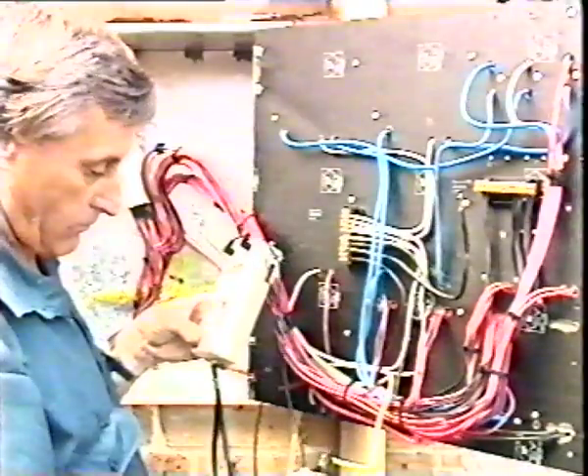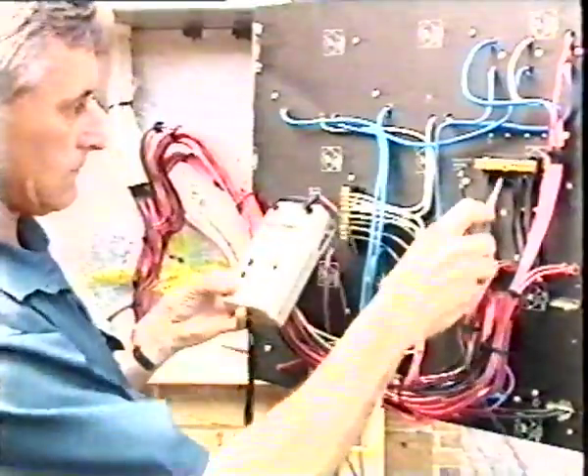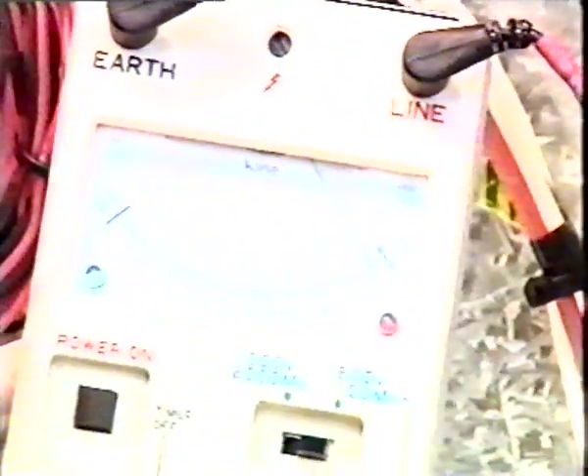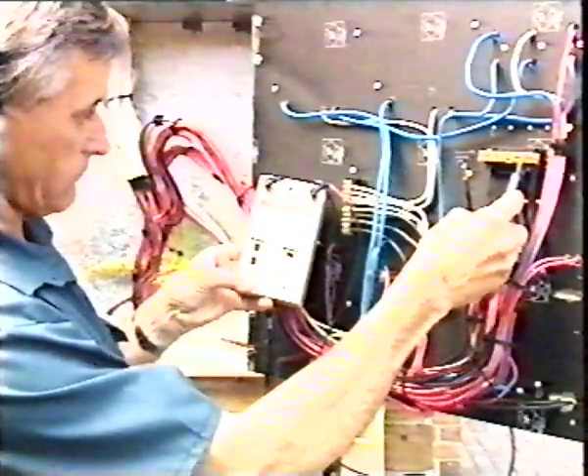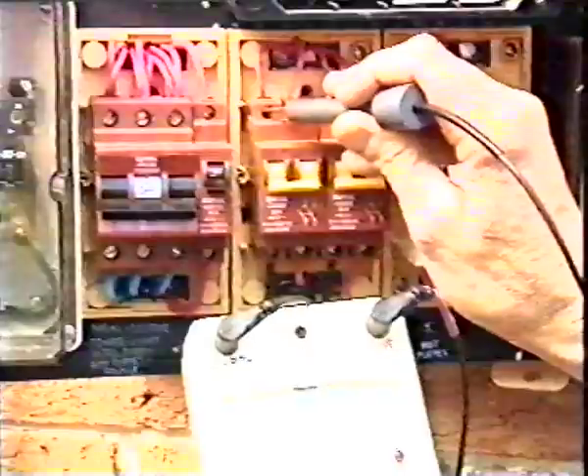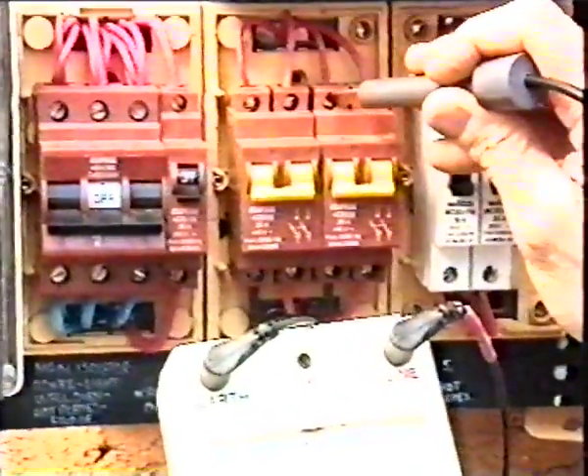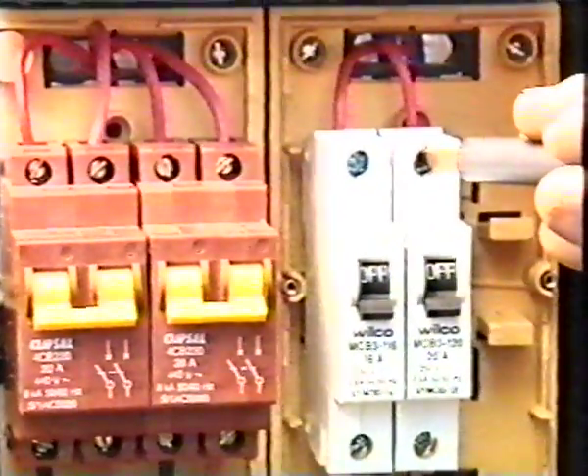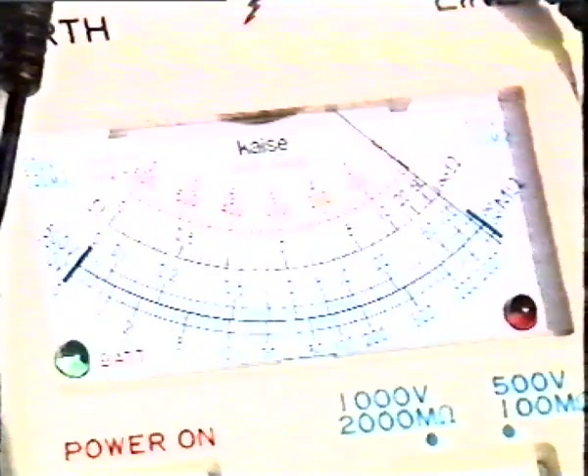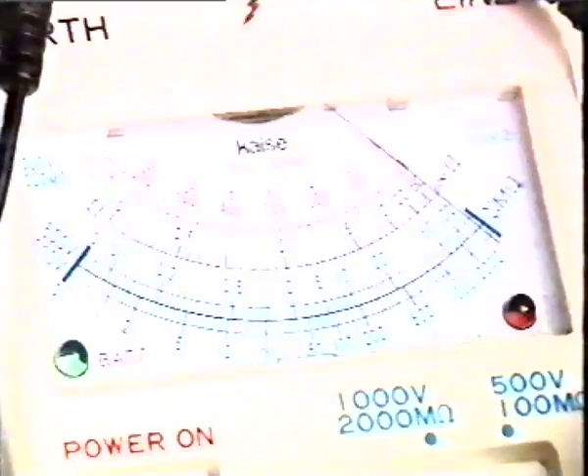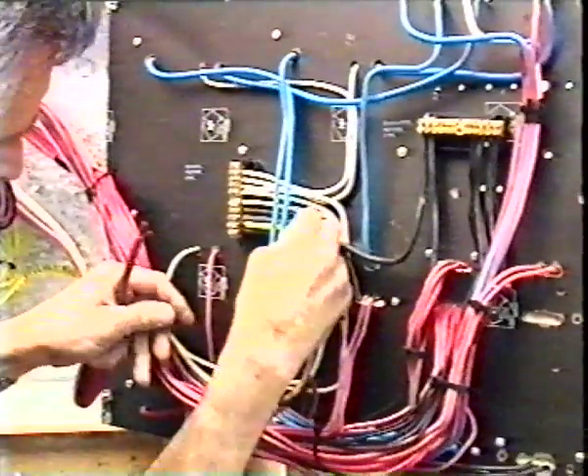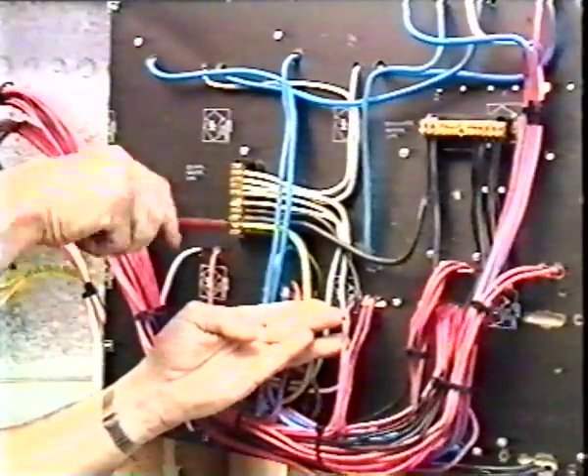Connect the insulation resistance tester between the main earthing conductor and all neutral conductors, either as a group at a neutral link or as individual consumers' mains, submains and final subcircuits. Then all active conductors connected to each phase, either as a group or as individual consumers' mains, submains and final subcircuits as before. Close switches in all circuits. Where two-way and intermediate switching is installed, these switches must be operated to ensure that all conductors are tested. Now test for insulation resistance. A reading of at least 1 megohm is generally required. Reconnect the main earthing conductor to the MEN connection and the neutral link.